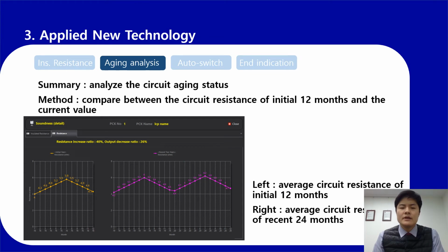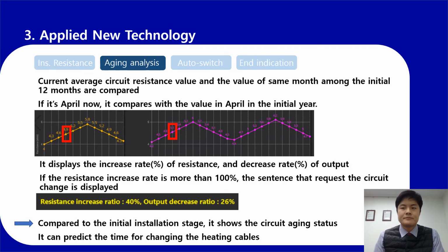As explained, existing technology cannot find out how much the cables are aged before the accident happens. Our new technology automatically analyzes the change trend of the resistance value and shows the circuit's current aging status. It helps the manager to predict the time to change the circuit. So, before the freeze accident happens, the manager can prepare the budget of the year and manage the facility with plans.